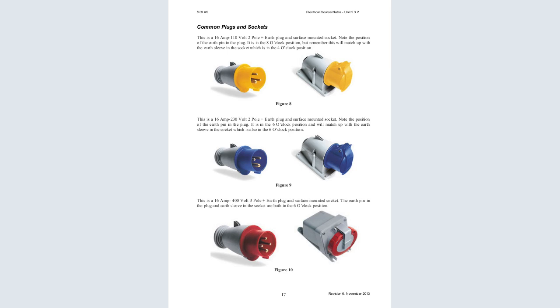Now the common plugs and socket outlets. You will normally be meeting these plugs in the industry, because these are the plugs that are used for high three-phase voltage, high loads. So it is 16 amperes, 110 volts, a two-pole earth plug and surface mounted socket. Note the position of the earth pin in the plug, in the 8 o'clock position. Remember, these will match up with the earth sleeve in the socket, which is in the 4 o'clock position. So you can see it.